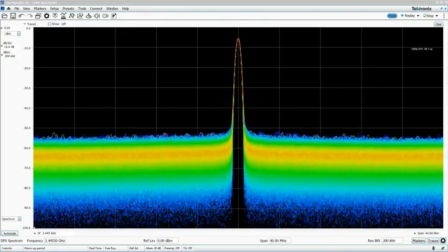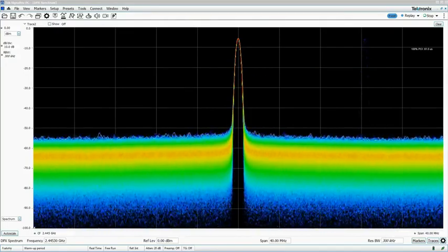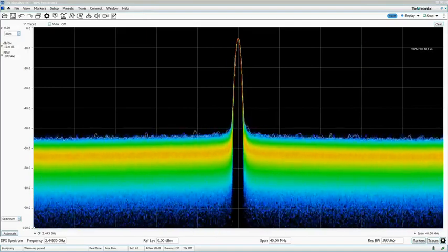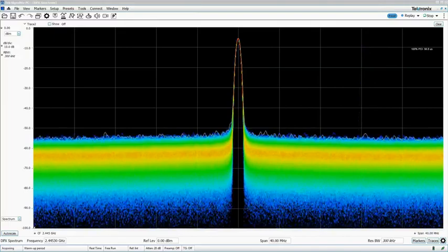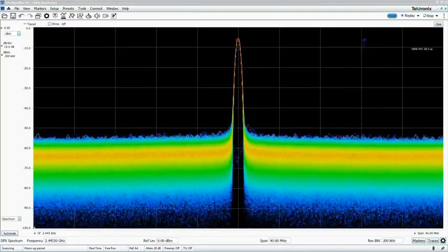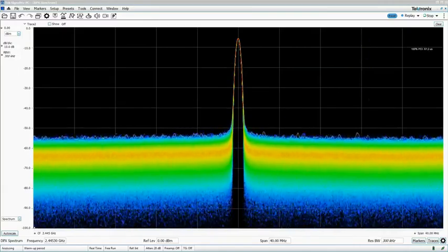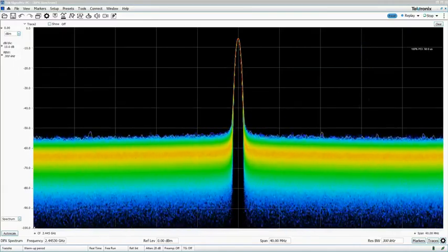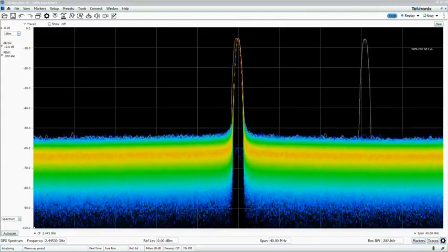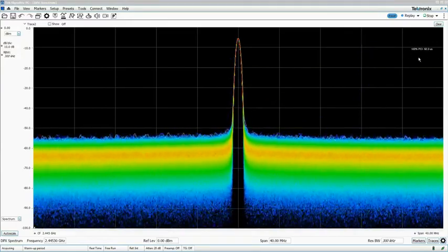Real-time spectrum analysis is the practice of using specialized algorithms implemented in either hardware or software to significantly increase the number of spectrums processed per second. The main specification associated with real-time spectrum analysis is minimum signal duration for 100% probability of intercept. Thankfully, this is often abbreviated as POI. The POI specifies the shortest signal that can be reliably captured and displayed.